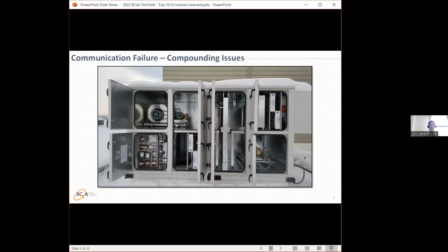I noticed there was no hardwired freeze stat on two downstream heating coils that were in the space. I'm glad the heating coils were in the space and not up in the unit - typically anything east of the Cascades, I always say don't have hot water coils in a roof if you can avoid it, and they had it out in the space. That's great, but there was no hardwired freeze stat.